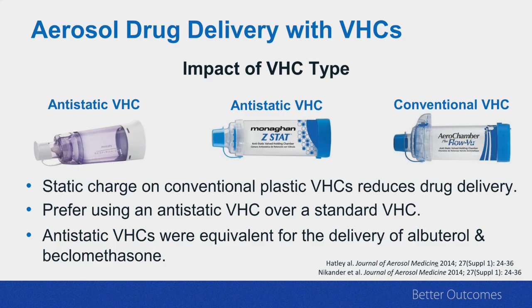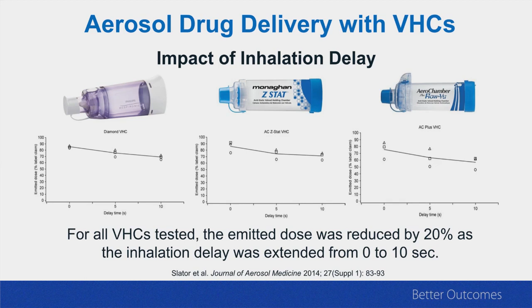What about inhalation delay? That makes a difference. If your patient delays his inhalation by 10 seconds, the emitted dose will be reduced by 20%. And it will happen with any type of valved holding chamber that you use during treatment. So make sure that your patient starts his inhalation as soon as you actuate the pMDI.